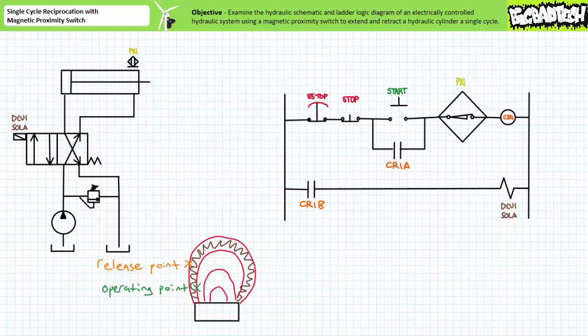Often these additional power wires are not explicitly drawn in the ladder logic diagram since they don't make decisions, however they are critical for proper functionality. If the diagram does feature those connections, you might see two additional wires leading outside the diamond-shaped symbol directly connected to the vertical upright rails of the ladder logic. Additionally a magnetic proximity switch only detects magnetic objects. To detect a non-magnetic object without touching it you may need a capacitive proximity sensor using an electrostatic field, or a photoelectric eye using light. Finally the ability to detect magnetic objects is both a blessing and a curse — such a switch could be falsely triggered by a dirty industrial environment or an errant magnetic object passing within its range.